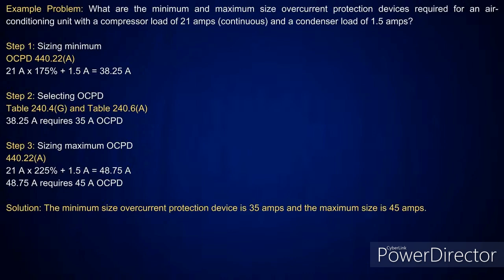Mm-hmm. And if you drop to too low of an overcurrent device, then that overcurrent device is going to nuisance trip. That's right. Sure. So then you know you need to go up. That's why they give you these different options. Right. Now, the other thing I'll say here is this is just like motors. When I do a motor, you take the largest motor at 125%. All other motors are added at what? 100% for sizing the conductors.